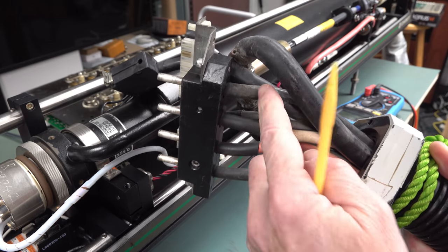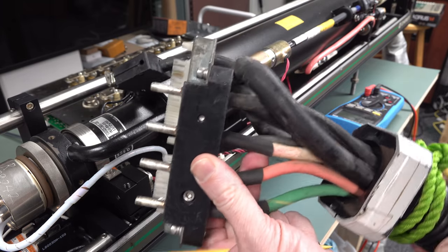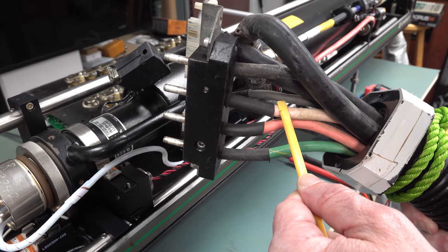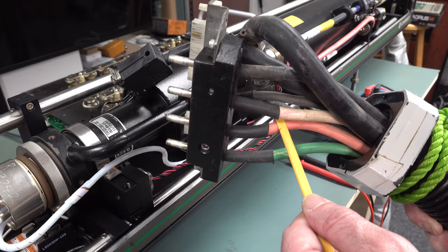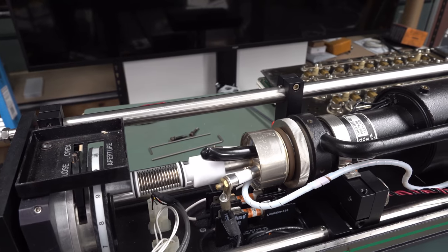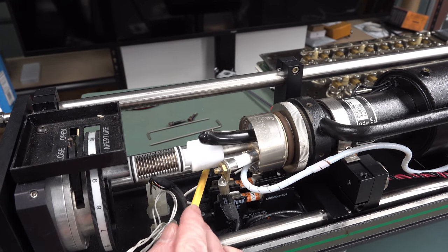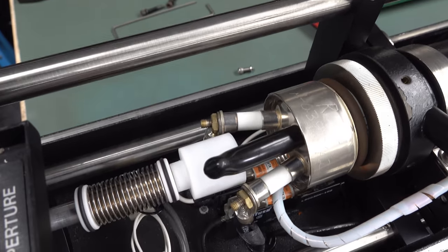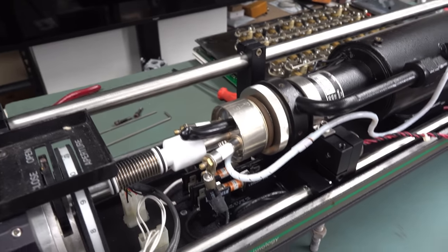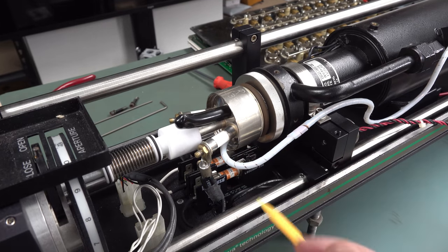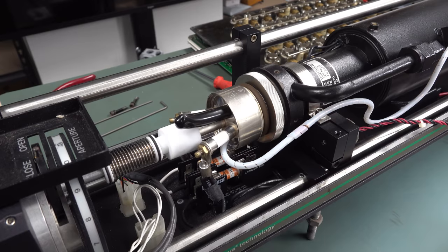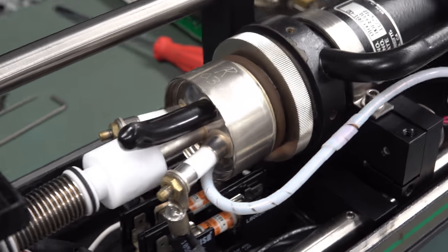So they've got this rigid optical thing. Is it like a rigid fiber or something? I'm not sure. Leave it in the comments down below. But it looks like it's got like a copper outer sheath or something. But it's gotta be tapping off the optical as part of the resonator in there. So it's tapping that off and detecting that. Why it actually has this tube on the end of it, I'm not actually sure what the deal is there. If you do know, laser experts, leave it in the comments down below. Okay, so let's follow the money on these big bad boys here and see what's what. Our black and our white wires here, these are for the filament, the heater filament itself. And the red is the anode, green will be earth.